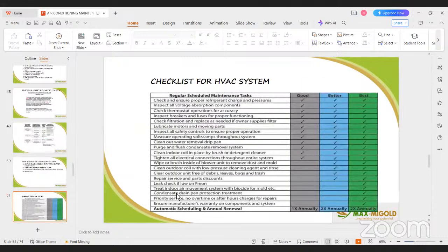Then checklist. Checklist is what you need to give to your technician every day. What must you check when you come every morning? You must check your refrigerant if it's okay, check your cable if it's okay, check AC if it's cooling properly, check your control that the batteries are there, check there's no noise in your AC, both indoor and outdoor, check the stand if it has not been shifted. That is what checklist is for.